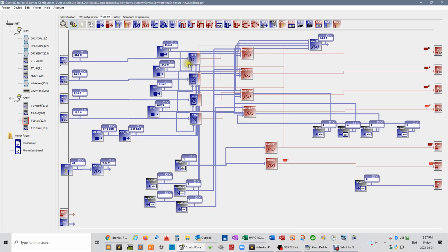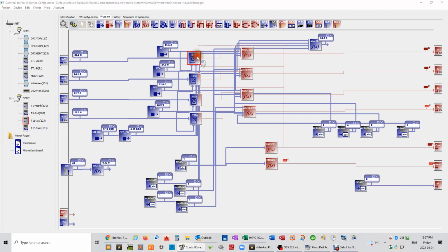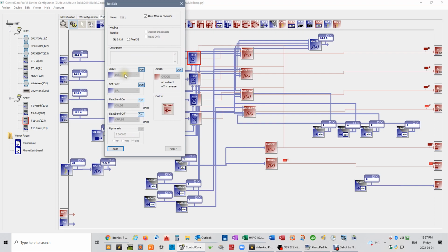So I talked earlier about the block type T-stat. This is where it is taking the current indoor air temperature, the set point, and your on and off dB. That deadband means how far above and below the set point it's going to allow the temperature to get before it acts on it. And then it's saying what it's going to do and output.